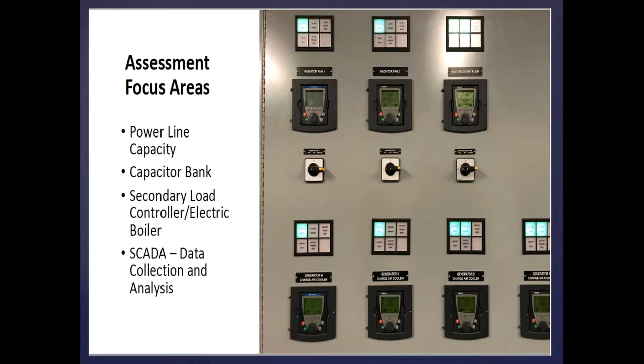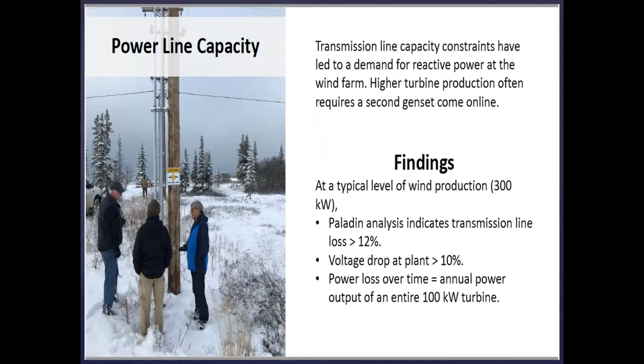The study helped us articulate the problems, examine alternatives, and make ranked recommendations. The big finding was that if we increase our voltage, we'll significantly reduce our line loss and eliminate the voltage drop at the plant. Over time, just by increasing our voltage, it will save the annual power output equivalent to an entire 100 kilowatt wind turbine's annual production.